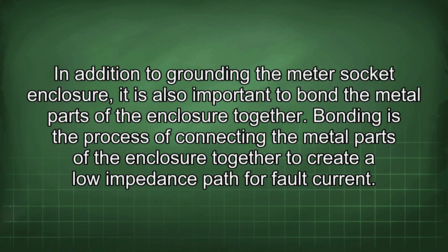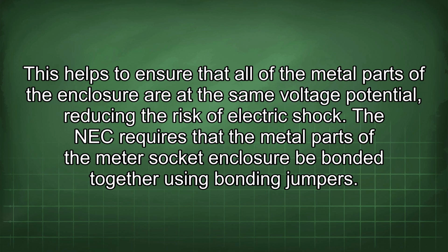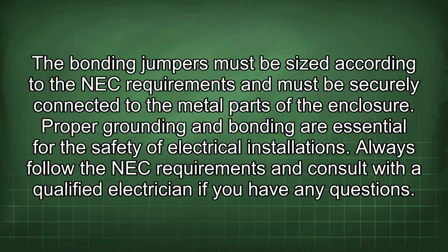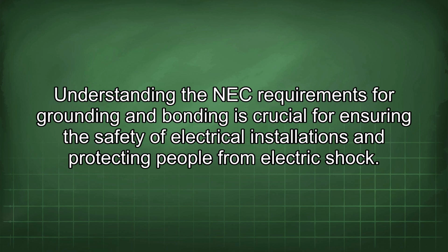In addition to grounding the meter socket enclosure, it is also important to bond the metal parts of the enclosure together. Bonding is the process of connecting the metal parts of the enclosure together to create a low impedance path for fault current. This helps to ensure that all of the metal parts of the enclosure are at the same voltage potential, reducing the risk of electric shock. The NEC requires that the metal parts of the meter socket enclosure be bonded together using bonding jumpers. The bonding jumpers must be sized according to the NEC requirements and must be securely connected to the metal parts of the enclosure. Proper grounding and bonding are essential for the safety of electrical installations. Always follow the NEC requirements and consult with a qualified electrician if you have any questions. Understanding the NEC requirements for grounding and bonding is crucial for ensuring the safety of electrical installations and protecting people from electric shock.